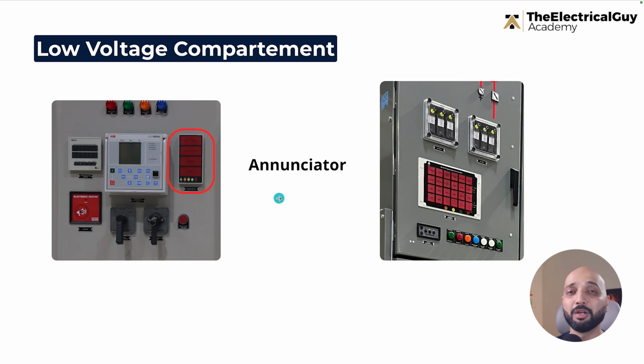Now this annunciator may or may not have a hooter inside it. When an abnormal condition comes, that specific window will start blinking, and it may make noise. If there is no hooter provided inside, then we can have a dedicated electronic hooter which will make noise so that the customer can know which panel is faulty and what kind of fault has occurred. That specific window will start blinking when the fault is there. So that's the purpose of the annunciator.